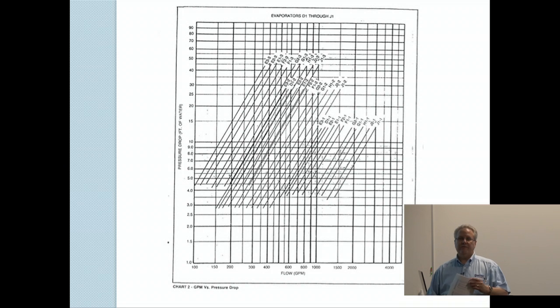This may look like Greek to you, but every chiller manufacturer provides a nomograph like this. When you're taking that pressure reading across the condenser, for instance, this is an evaporator. You take your pressure drop across the evaporator, let's say it's 15 foot of water, and you come across here and find this particular vessel, it's easier to see this one, this J1-2 vessel. Then you come over to that line, come down, and it tells you what your flow is, 1,000 GPM. So you can highlight the particular line that applies to your chiller, and knowing the differential pressure, be able to determine the flow going through that chiller.